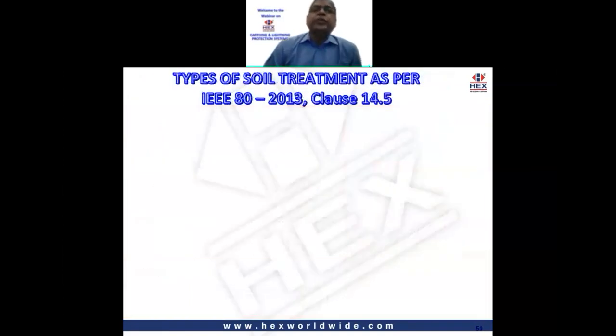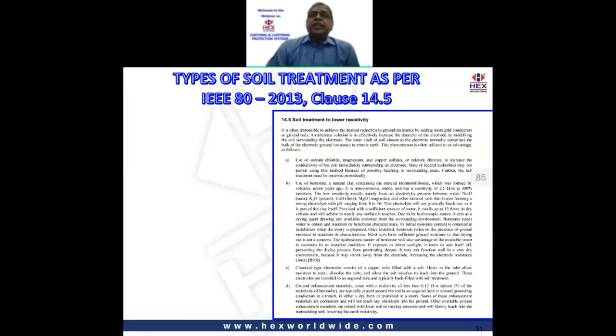Let's go on to soil treatment. Clause 14.5 of IEEE states that it is often impossible to achieve the desired reduction in ground resistivity by adding more grid conductors or ground rods. But as an alternate solution, various types of soil conductivity improvement materials can be used. Subclause A states that salts can be used to do this, but it also cautions about its disadvantages due to leaching and the regular maintenance that is required.